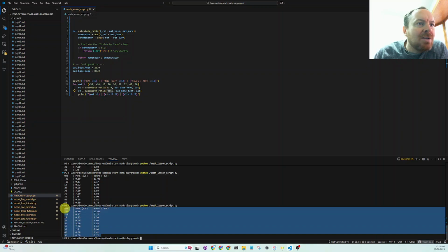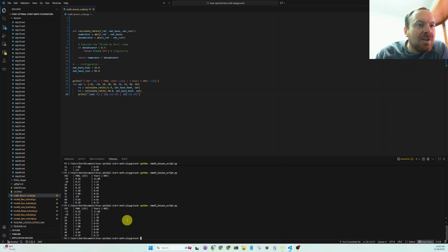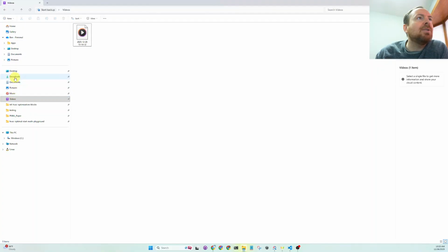So I am going forward to actually using extreme high and low limits that are almost like design day parameters in HVAC. Else this mild value of 32 can have some adverse effects. So this works. This is what I'll be using in my optimal start algorithms, which I'll show you in a minute.